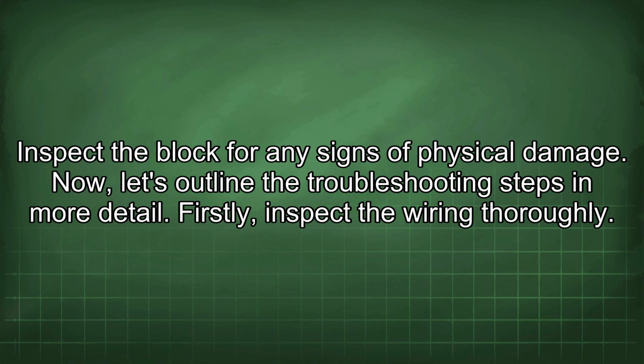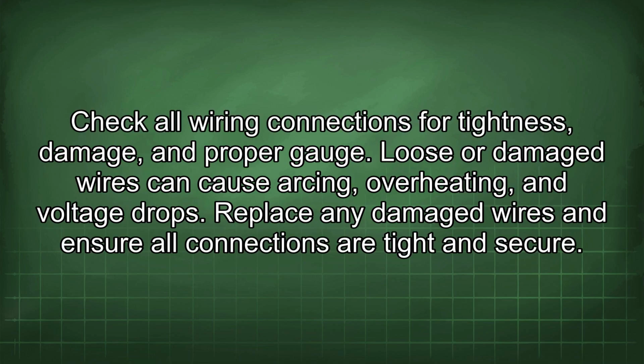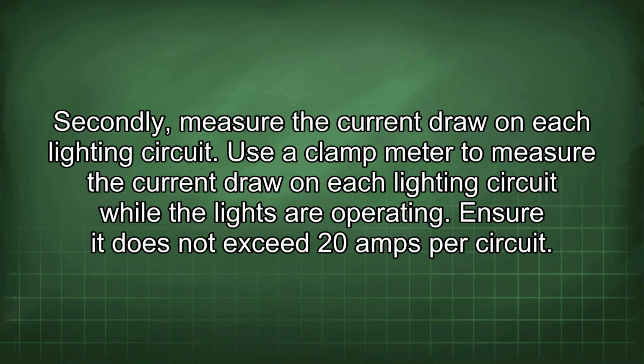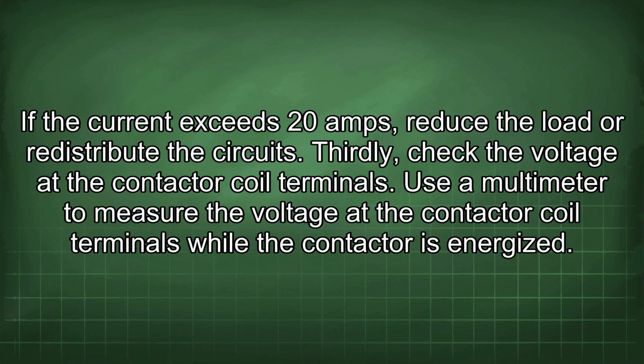Now let's outline the troubleshooting steps in more detail. Firstly, inspect the wiring thoroughly. Check all wiring connections for tightness, damage, and proper gauge. Loose or damaged wires can cause arcing, overheating, and voltage drops. Replace any damaged wires and ensure all connections are tight and secure. Secondly, measure the current draw on each lighting circuit. Use a clamp meter to measure the current draw on each lighting circuit while the lights are operating. Ensure it does not exceed 20 amps per circuit. If the current exceeds 20 amps, reduce the load or redistribute the circuits.